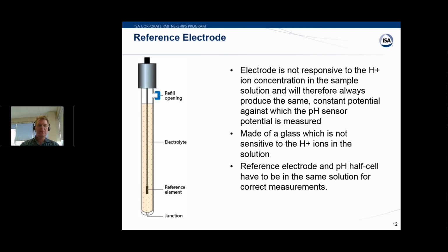So if we're doing this measurement, right, we need to have a reference electrode. And so in a very high sensitivity, they have separate reference electrodes. And basically the electrode is not responsive to the concentration in the solution, but we have to create that difference, or the reference point. So the reference electrode is made of glass that is not sensitive to the hydrogen ions, and for that reason, right, it's a half cell where we have a constant junction gradually leaking or weeping out the electrolyte, which is why we have to have a refill to replenish the electrolyte. So effectively we are creating a small cell, right, between the reference electrode and the actual pH measurement electrode.